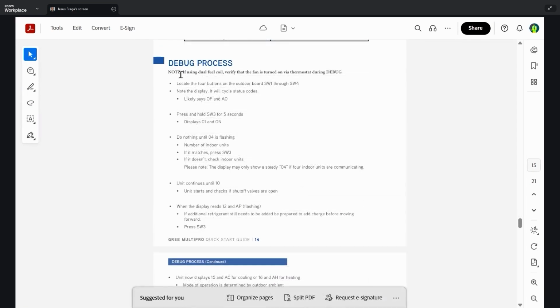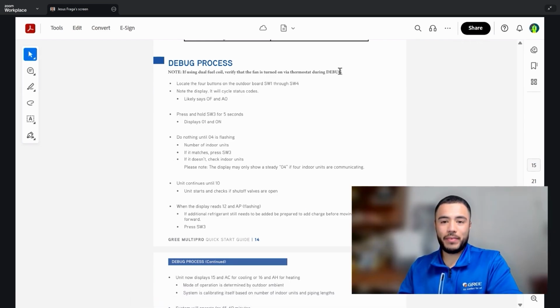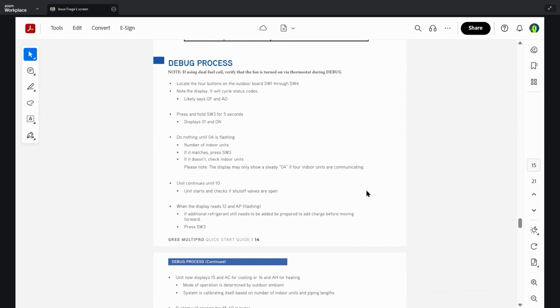The debug process is pretty much the same as the 410A. So we know that once we have the system piped together, pull the vacuum, and we're ready to do the actual start. This is after we've released the charge and added any additional refrigerant if needed. We're going to verify that the outdoor unit says AO along with the indoor unit and its wired controllers. So everything in the system from the outdoor unit to the indoor units should show an AO. Once that's verified, you're going to go through the debug process. As you reach each step, there's an explanation here as to what they mean. And if you get anything other than this, likely it's going to be an error code.